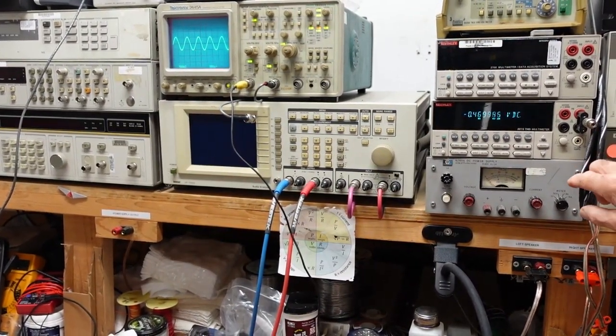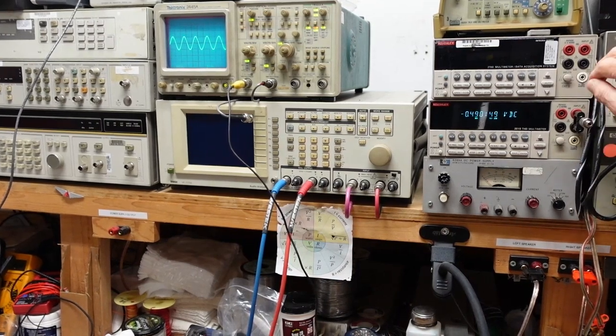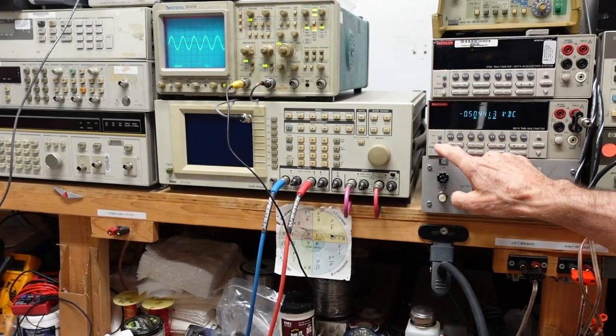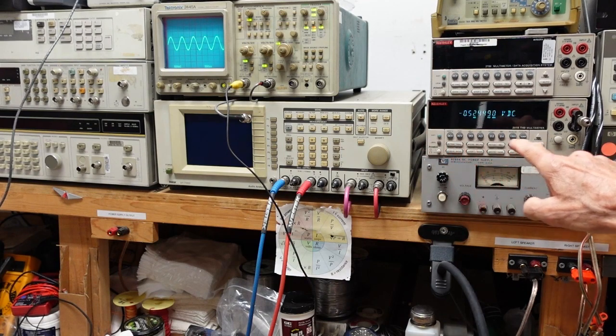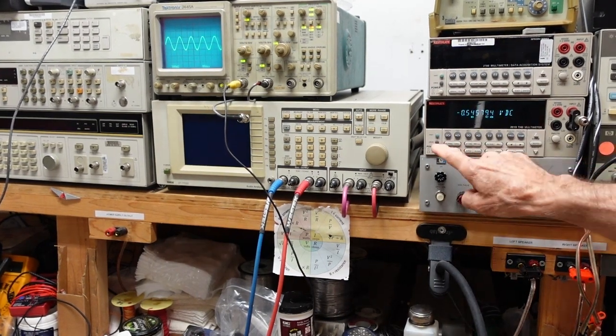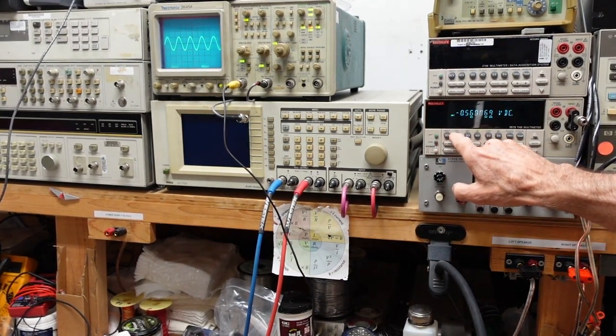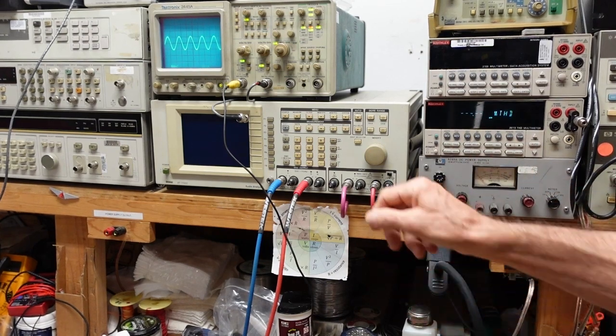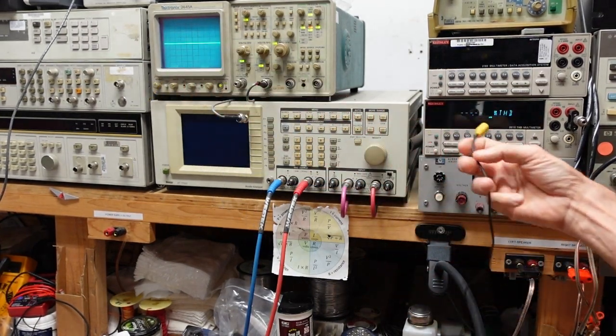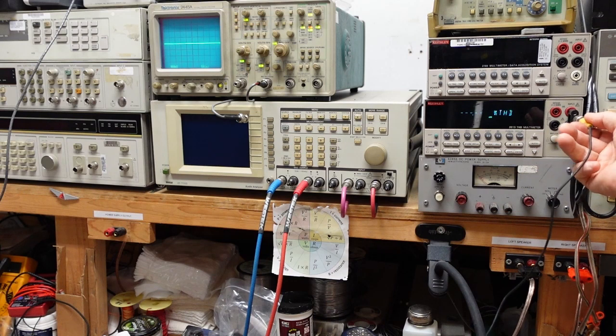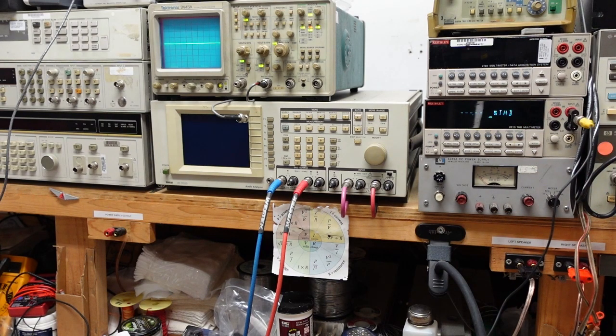And we're going to use the Keithley's distortion function to see how low we can get that. So our THD on the meter is accessed by hitting the shift key in AC volts. And that puts us into THD mode. We take the lead from the scope and put it in here and see what we get. So we have 0.3%, so we'll see if we can get that any better.